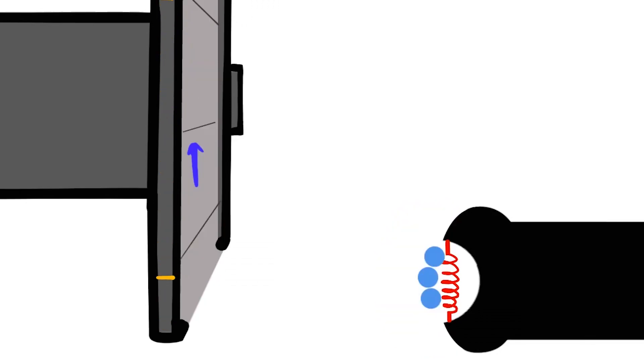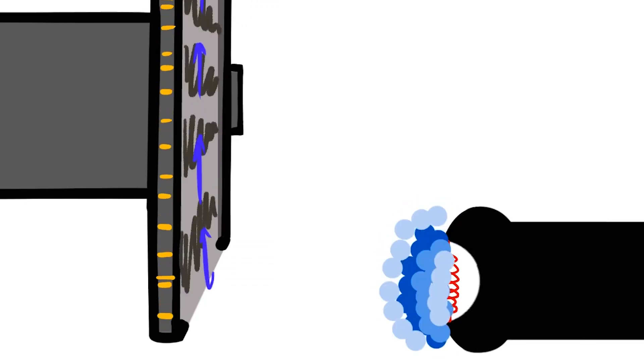Now, still within that first step, as you're pushing the x-ray button halfway down, you're also boiling off electrons at the cathode, specifically at the filament. The x-ray generator is being supplied with amperage, or electric current, to the filament, which begins to boil off electrons. This is all happening inside a vacuum, so the electrons are just bundling in a cloud — they call it thermionic emission. It's bundling in a cloud right around the filament, just putting out electric current, not necessarily going anywhere yet.